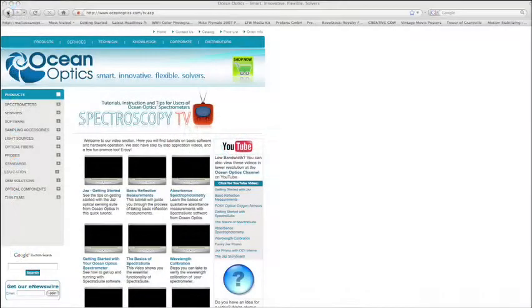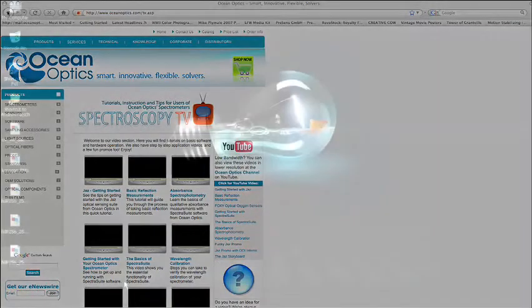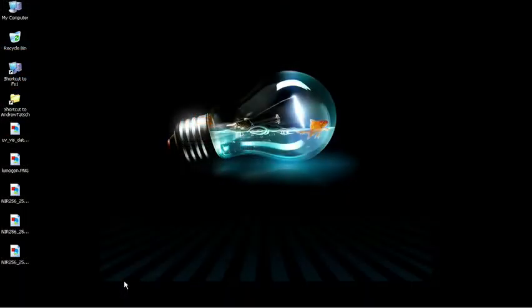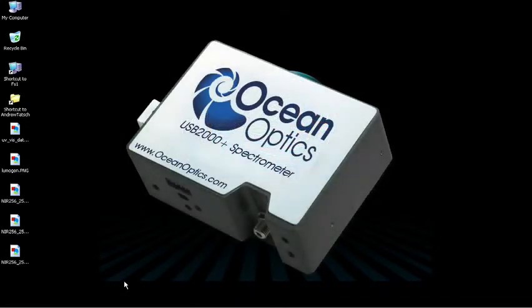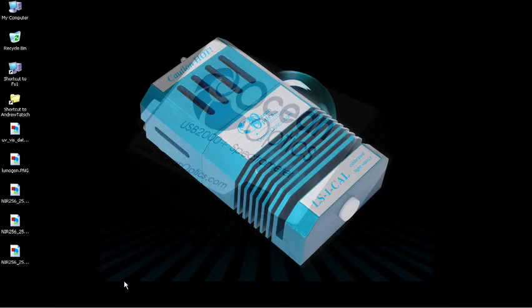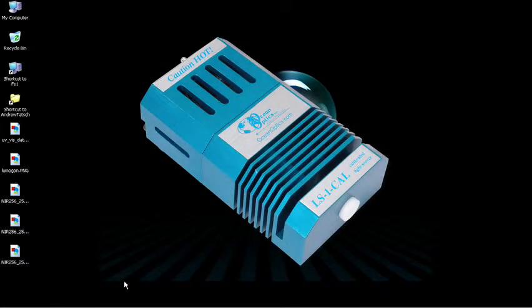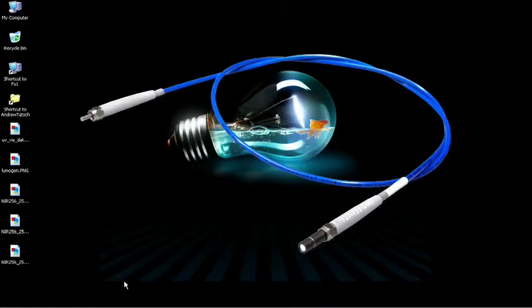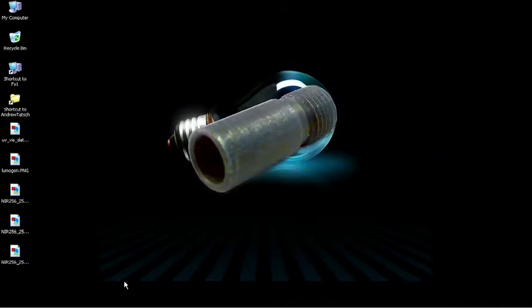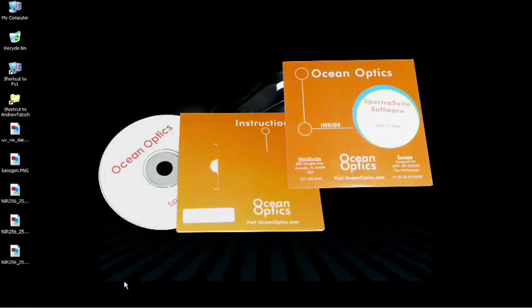If not, please log on to oceanoptics.com and download the tutorial for getting SpectraSuite up and running on your PC. For performing this radiometric calibration, we will use a USB 2000 Plus spectrometer, LS1 Cal calibrated light source, a 600 micron Vis-NIR fiber optic patch cable, bare fiber adapter, and the SpectraSuite software.